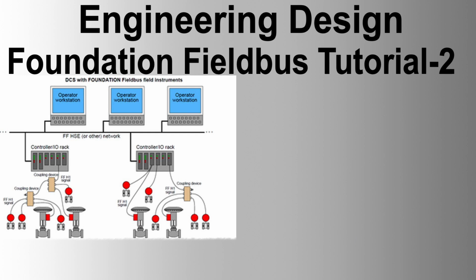View 1, operation dynamic. List of dynamic parameters necessary for running the plant by operators. View 2, operation static. List of static configured parameters that may be necessary to show operators along with the dynamic parameters. View 3, all dynamic. List of all dynamic parameters that may be used for detailed display or diagnosis. View 4, other static. List of static parameters that may be useful for configuration and maintenance purposes.